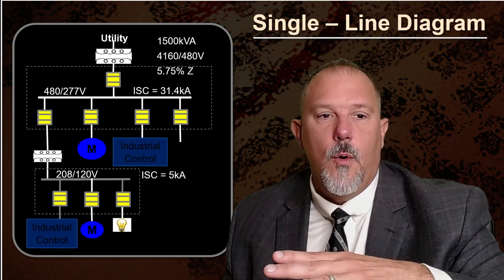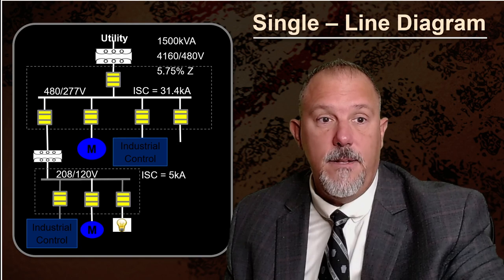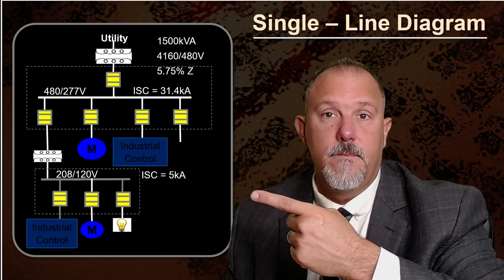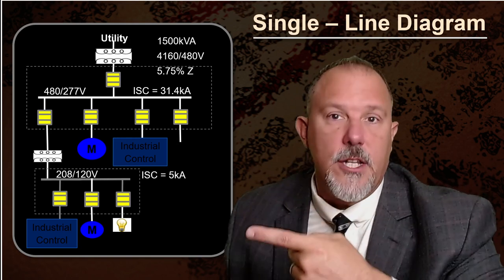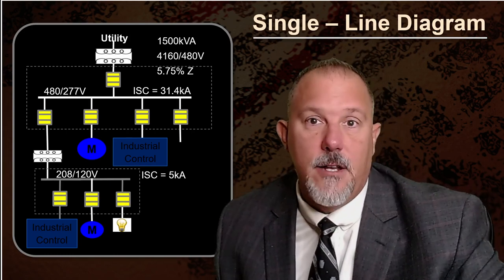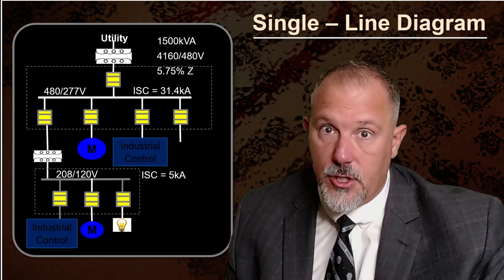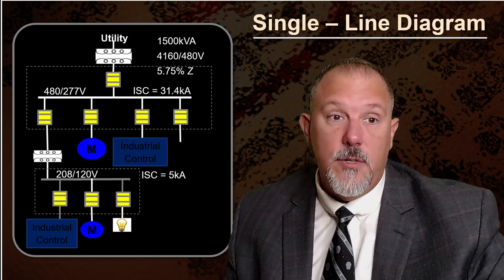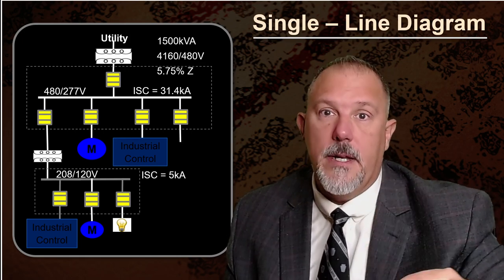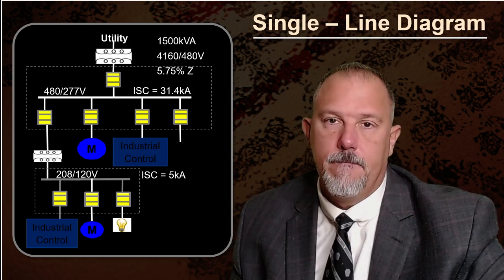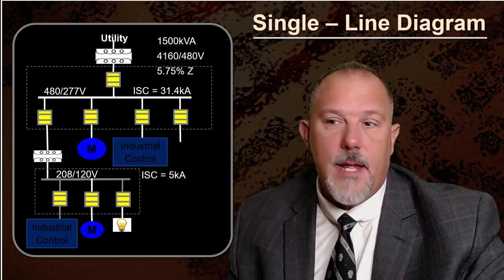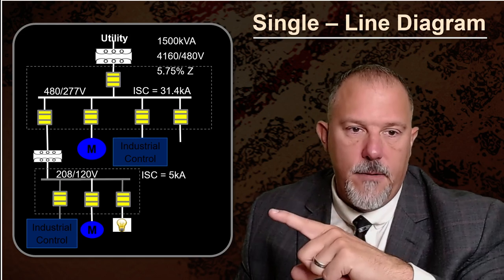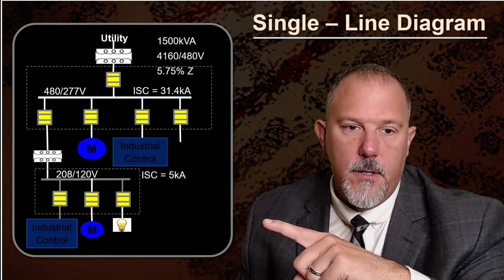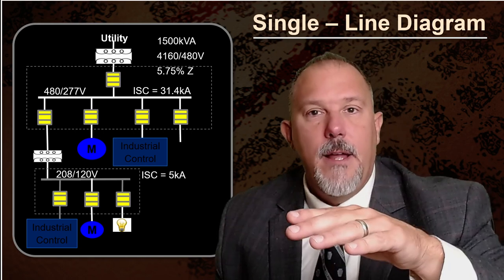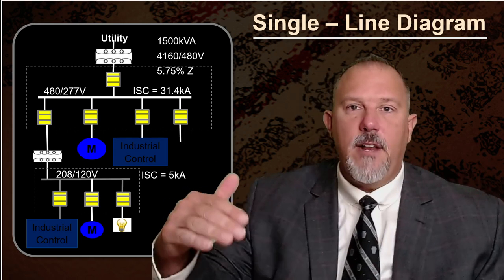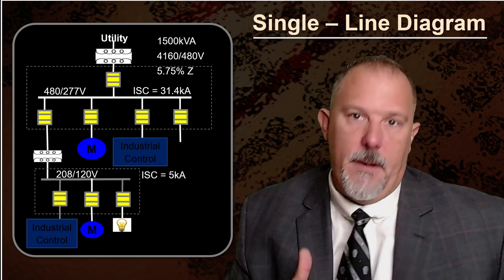Understanding how to establish an electrically safe work condition, you need this. Which overcurrent device, which switch, which circuit breaker do you need to lock and tag out? Or which circuit breakers, which switches do you need to open and lock and tag out? It may be multiple. Understand that the panel board that you're working on, that 208 volt panel board on the secondary of that transformer, my severity from incident energy just went up.